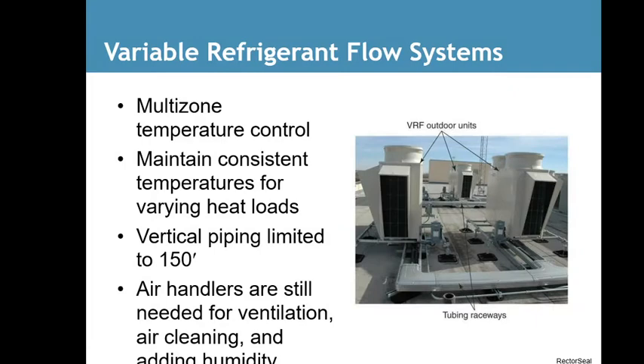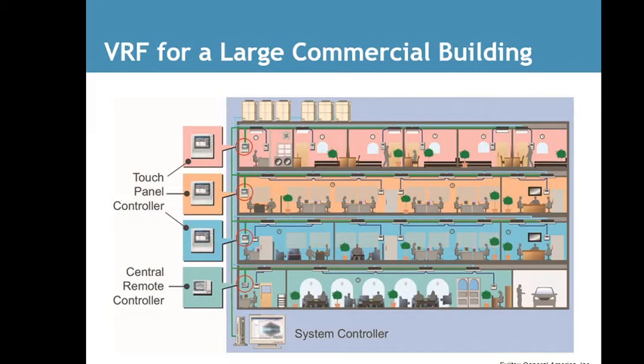Variable refrigerant flow systems: multi-zone temperature control, maintaining constant temperatures for varying heat loads, with vertical piping limited to 150 feet. And they're talking about anything, for example drainage pipes, water lines leading up for cooling, or gas lines. They're limited because of the roof movement. Air handlers are still needed for ventilation, air cleaning, and humidifying. VRFs are for large commercial buildings. This gives you a little breakdown of how it works.